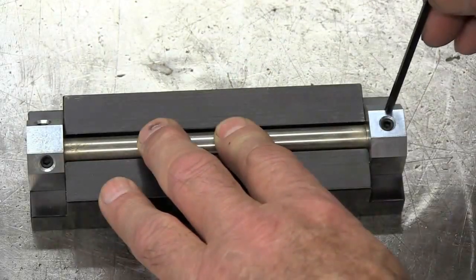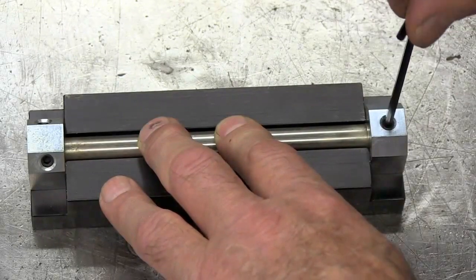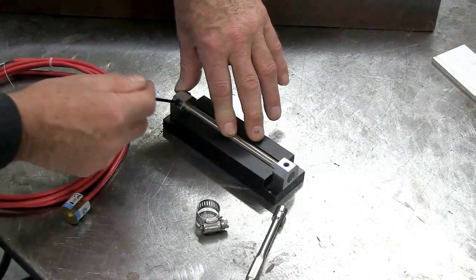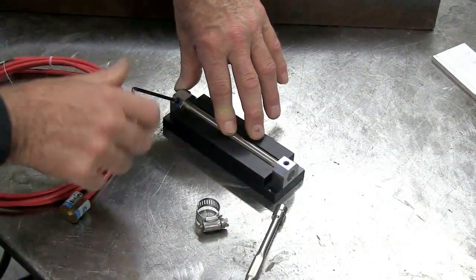It's put into this fixture here to get the correct orientation and length. Then we take this Allen key, snug the screw onto the end block, maintain this tight up against this fixture. Snug, do not tighten, just snug them up. That's it.